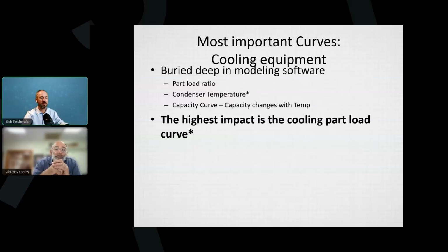And your heat pumps are basically garbage when it's 20 degrees Fahrenheit or below, when in reality, the modern heat pumps can run below 0 Fahrenheit. Mm-hmm. And so the capacity shrinks to 0 at like 25 degrees on some of the default curves. So anyway, that's an additional curve. And then all of those numbers tend to multiply by each other to figure out what the actual efficiency is. I've gone into the hourly inputs and actually done that to see how the curves are.